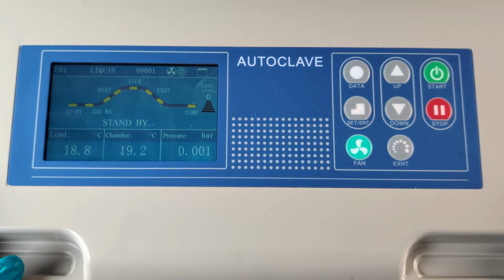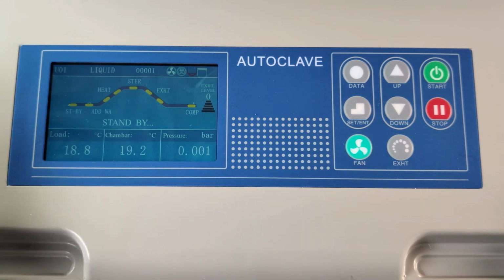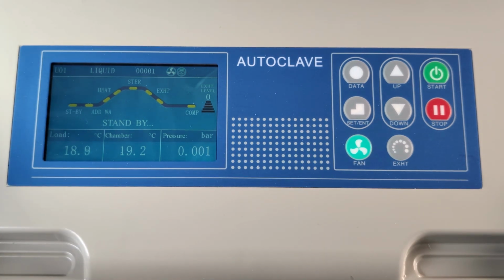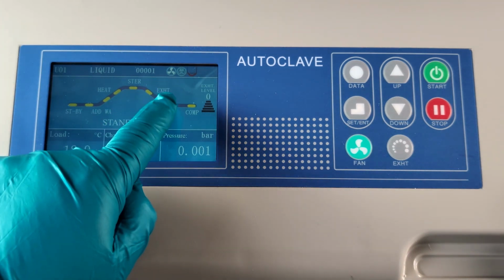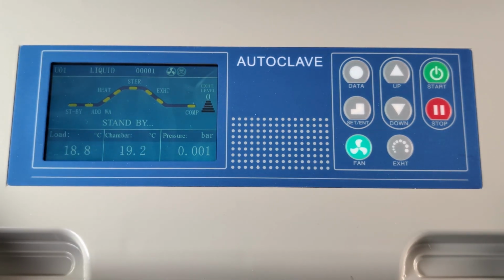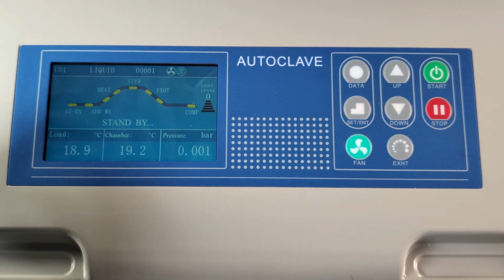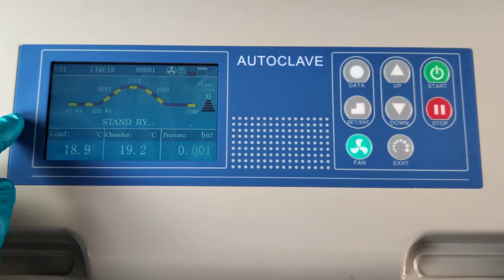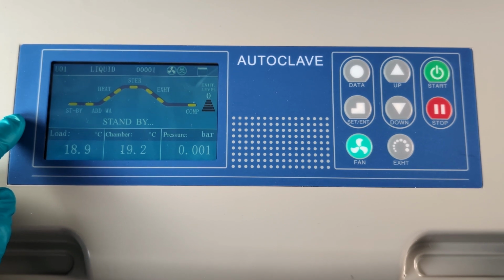Now, something that is very special about this autoclave is this last bit that you can see here, the exhaust level indicator. Most autoclaves at the end of the cycle, when they get to the exhaust part, will just open the vent. But if the steam goes out too quickly and the pressure drops too quickly, then there's a danger of the media or the agar or the liquid boiling over, because at a higher pressure it's a higher boiling point. So if you suddenly drop the pressure, then there's a chance of the liquid boiling over, and this could make a nasty mess in the bottom of the autoclave, which somebody has to clean up. Also, if it's expensive agar or media that you've got in there, it's an expensive mistake to make.